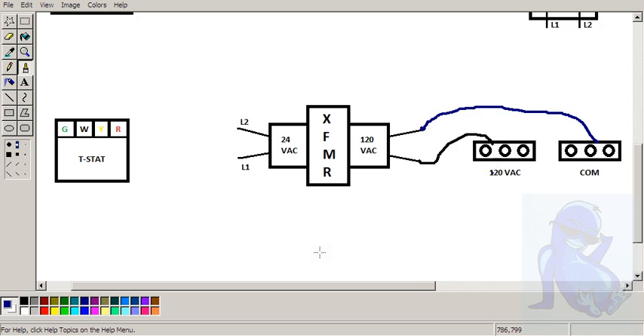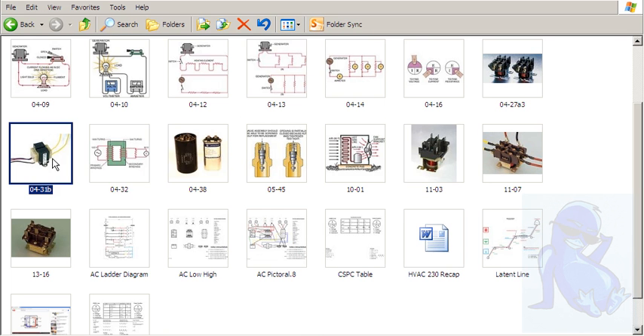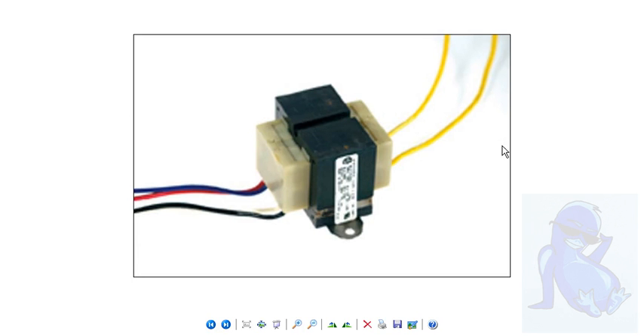So this is L1. This is my L1, and this is my L2. L1 and L2 high voltage hooked up to the high voltage side of the transformer. Let's take a look at that again. That is more than likely going to be on this side. There are 3 wires here because it's probably giving you the option of hooking up 120 or 240. It's giving you the option.